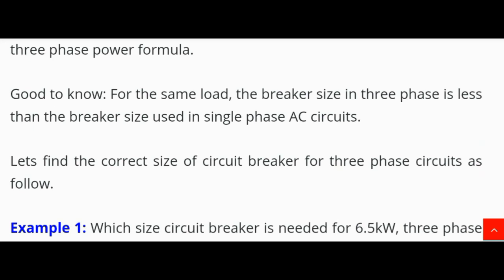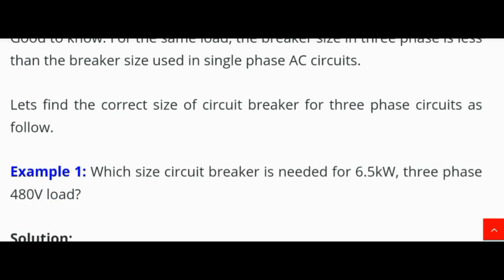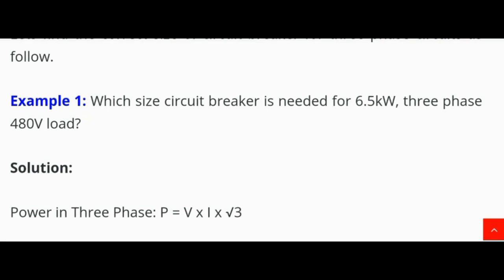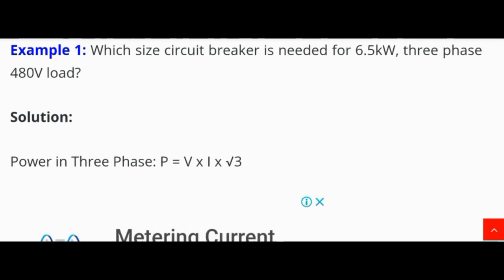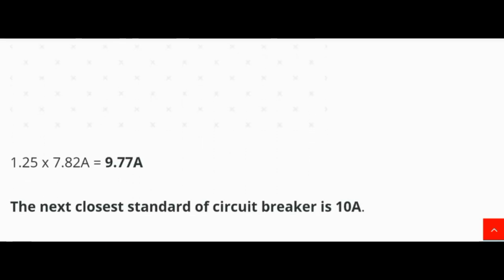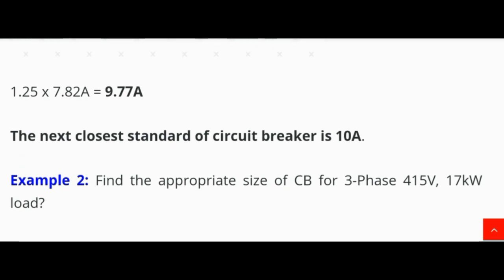Good to know: for the same load, the breaker size in three phase is less than the breaker size used in single phase AC circuits. Example 1: Which size circuit breaker is needed for a 6.5 kilowatt, three phase, 480 volt load? Solution: Power in three phase: P = V × I × √3. Solving gives I = 7.82 A. Then: 1.25 × 7.82 = 9.77 ampere. The next closest standard circuit breaker size is 10 ampere.